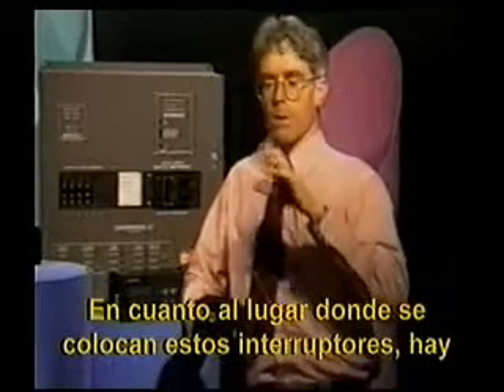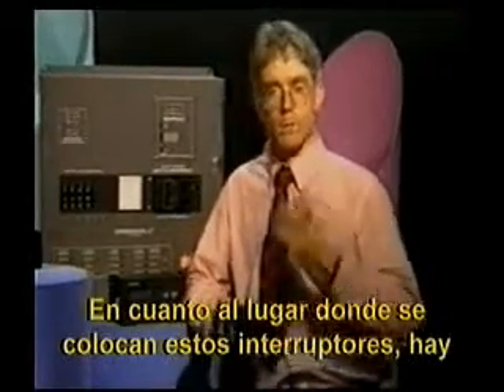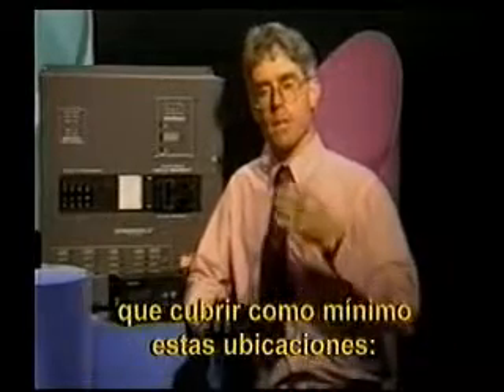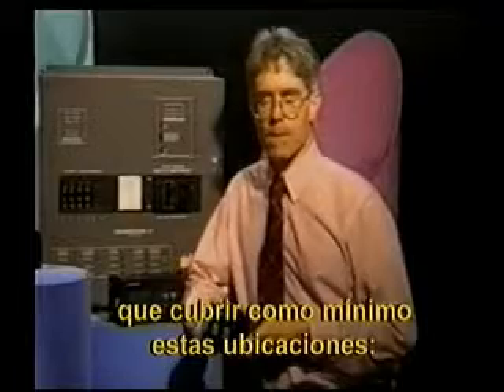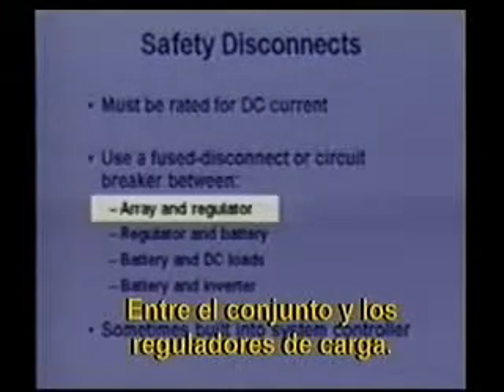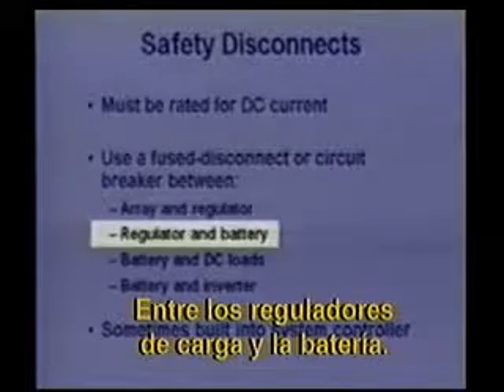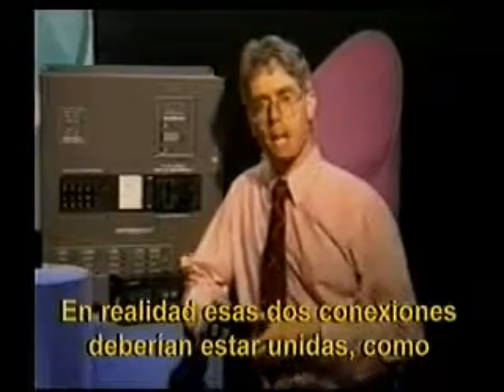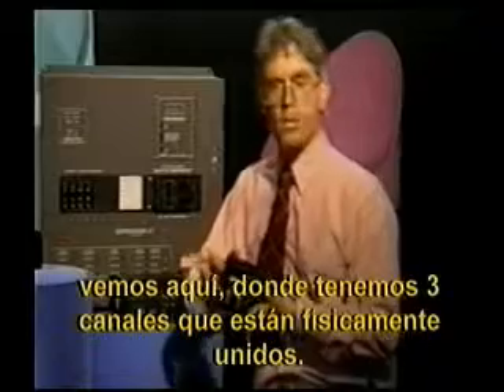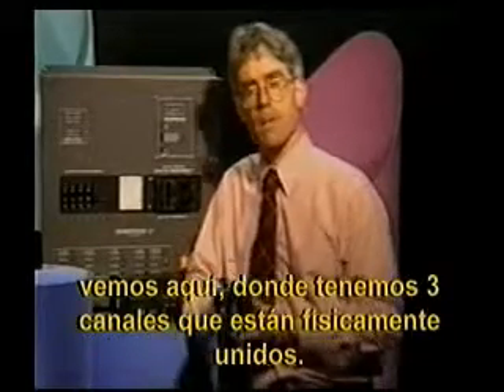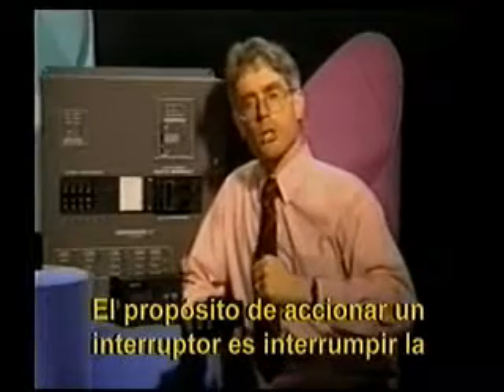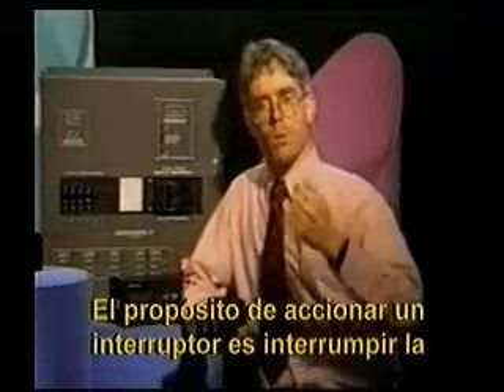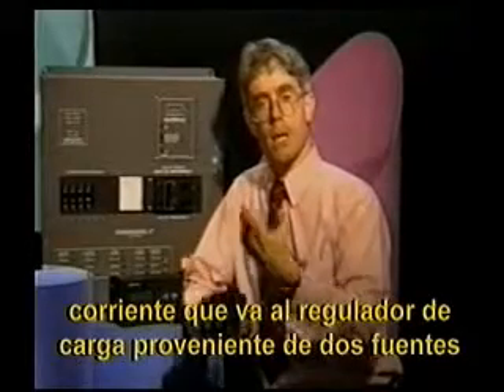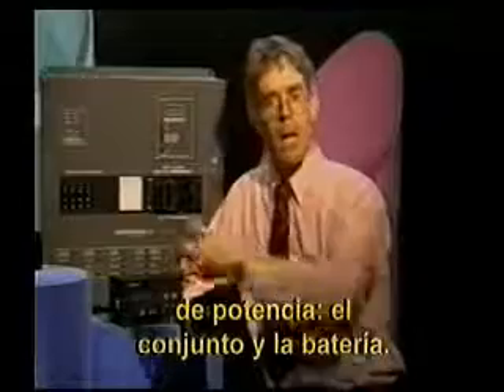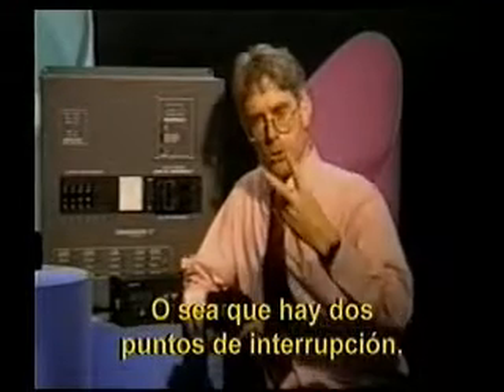In terms of where we locate these disconnect switches or circuit breakers in our system, there should be at least these locations that are covered. We want to disconnect between our array and our charge regulators, and between our charge regulators and our battery. Those two connections should actually be ganged together. For example, as shown here, we have actually 3 channels that are physically linked together. The point is that when we throw one switch or one circuit breaker, we're going to want to break the current flowing into the charge regulator from 2 power sources, the array and the battery. So there's 2 points of breaking.